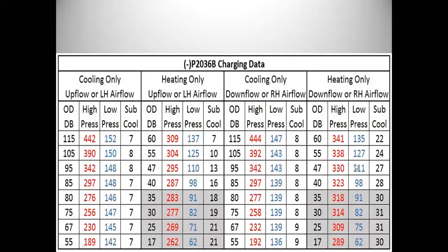So that kind of goes over some of the charging. The biggest thing I can tell you is when you're selling these, make sure your static pressure is correct. It is 1.0 or below. Ideally, the lower the better. It will make it run that much smoother. If it is high, it will put you in danger of inverter faults, even though the charge may look good. So it's kind of something to watch out for.